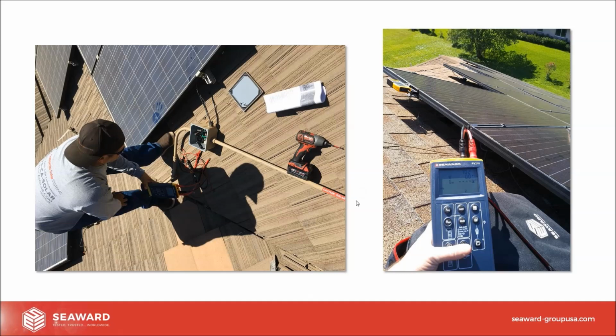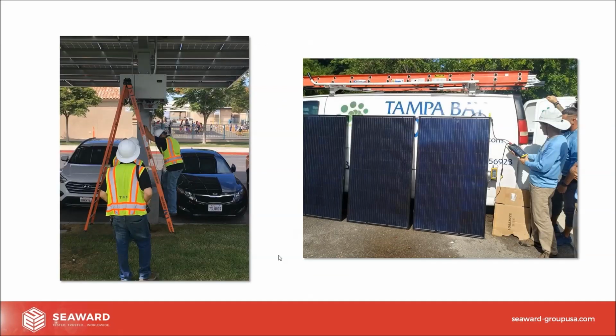We can make multiple connections to the array at multiple points. Carports are not a problem, as you can see here on the left-hand side, we just need to get up there, and we would connect the irradiance meter to the top of this carport. That's super important on these large carports with a steep incline, because the top panels will have a different irradiance to the bottom panels.